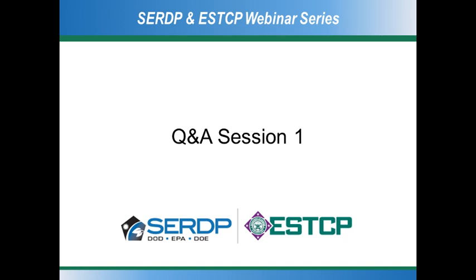Great, thank you. Can you tell us whether traditional ground loop designs can be retrofitted using reversing valves to provide similar thermal storage benefits? That's a great question, and the answer is not really. The problem is that your boreholes are typically piped in parallel, and so adding the reversing valves in and of itself is not going to help you. All that really will do is change the direction the water flows. If a U-bend, think of a capital letter U as the plastic pipe down in the ground, goes down to the bottom and the left leg is A and the right leg is B, water may be flowing down A and back up B, and now it's going to go down B and back up A, but that inherently doesn't change anything.